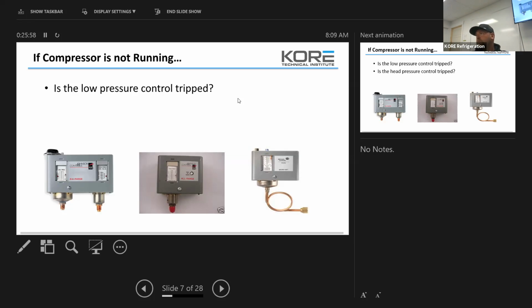Okay, that's how we're troubleshooting that. So all of these safety controls are there to protect that compressor. Oil fail is there to protect the compressor, head pressure is there to protect the compressor, low pressure is there to protect the compressor. So that's why those safeties are in play.